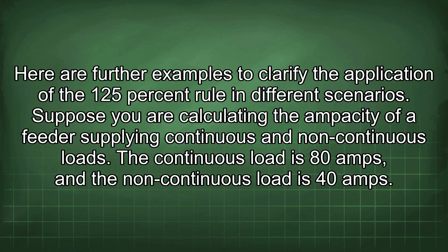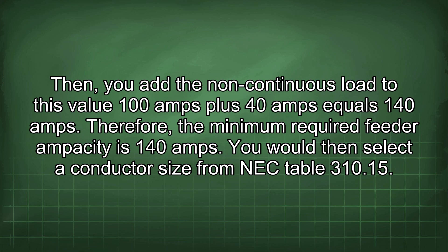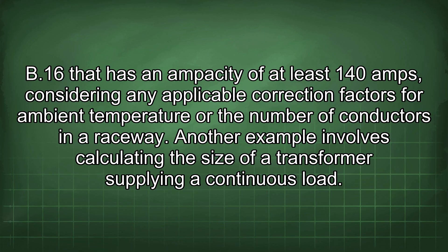Suppose you are calculating the ampacity of a feeder supplying continuous and non-continuous loads. The continuous load is 80 amps and the non-continuous load is 40 amps. According to the NEC, you must size the feeder to carry at least 125% of the continuous load plus the non-continuous load. First, multiply the continuous load by 1.25: 80 amps × 1.25 = 100 amps. Then add the non-continuous load: 100 amps + 40 amps = 140 amps. Therefore, the minimum required feeder ampacity is 140 amps. Select a conductor size from NEC table 310.15(B)(16) with an ampacity of at least 140 amps, considering any applicable correction factors.